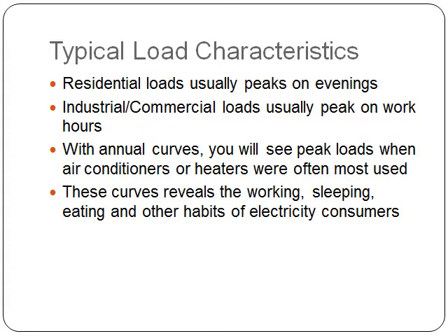Now, what are the typical load characteristics? Residential loads usually peak in the evenings. Industrial and or commercial loads usually peak at work hours because that's usually when they are being operated. With annual curves, you will see peak loads when air conditioners or heaters are most often used. Regardless of which curves and what time frame you're looking at, these curves often reveal the working, sleeping, eating, and other habits of consumers that consume electricity.